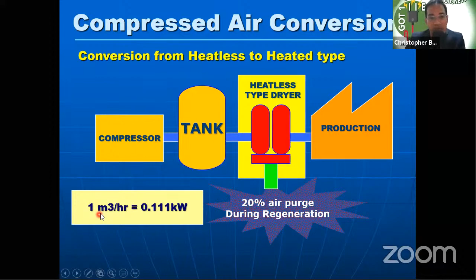So ang compressor, 1 cubic meter per hour na generate mong compressed air is equal to 0.111 kilowatt. So what we did, may mga heated type na adsorption dryers kaming na-source out. Comparing it with the 20% air purge, only 4% lang ng air purge ang kailangan mo. So using heat, a savings of 16% less purge or 66,860 kilowatt hour per month.